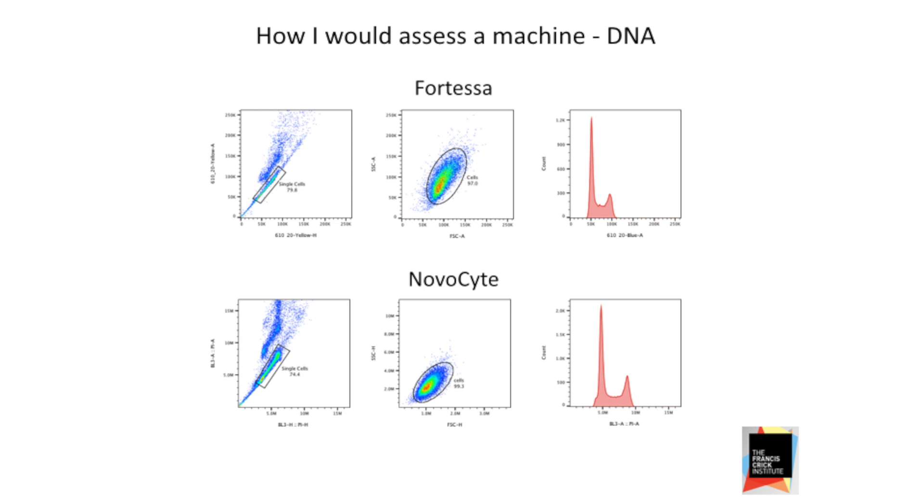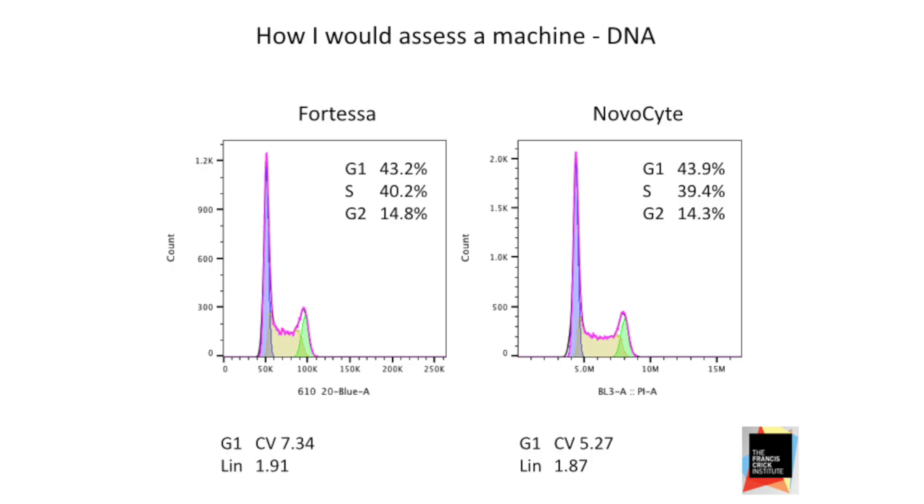My background is really in DNA analysis — that's one of the first ports of call when I get a new machine. I stain up some cells and run them with propidium iodide. Comparing a Fortessa, which is what I'd normally run my DNA on, we're getting very, very similar results with the NovoCyte. The CV of the NovoCyte is actually slightly better in this case, but we've not really found any difference. It's perfectly fit for purpose.